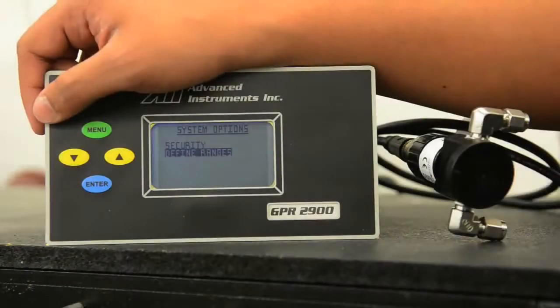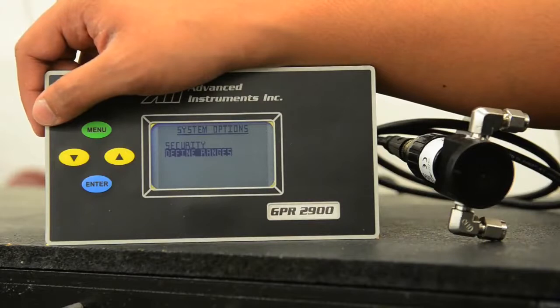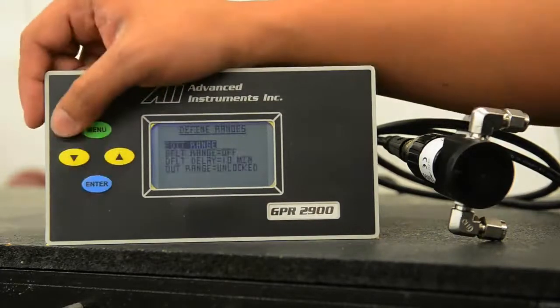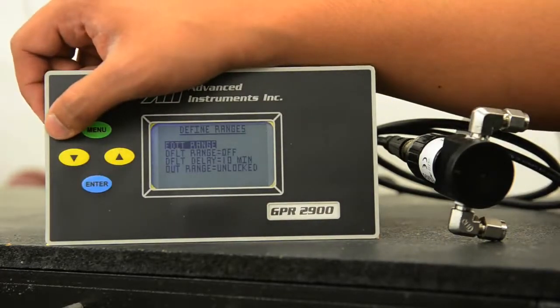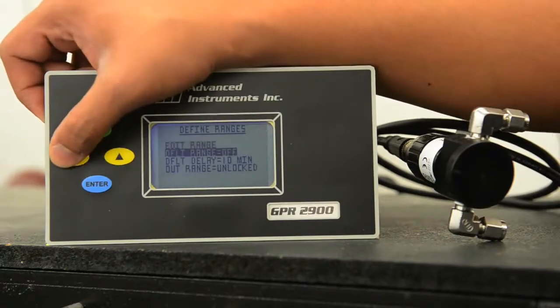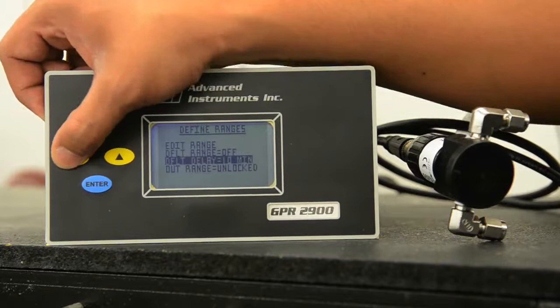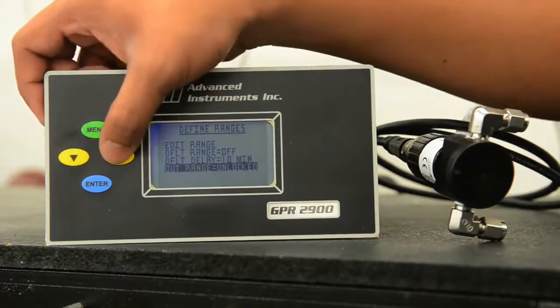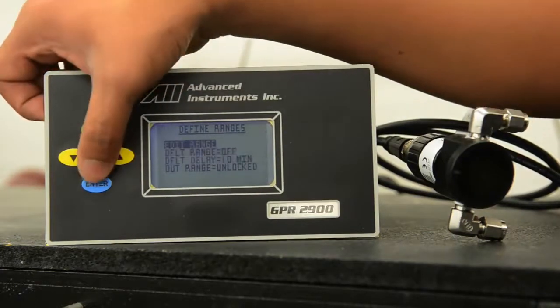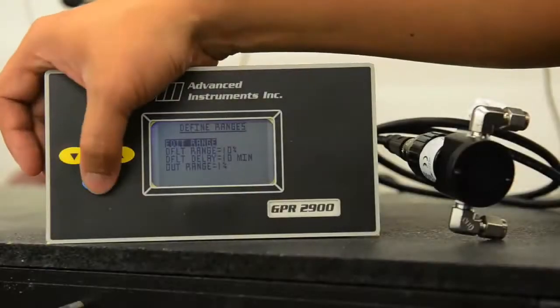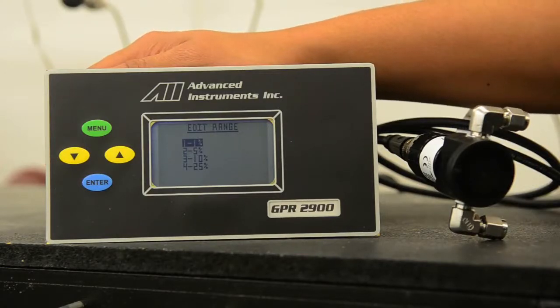Under the System Options menu, you also have the option for Define Ranges. If we select enter, we see on the Define Ranges menu we have Edit Ranges, Default Range option, a Default Delay Range option, and an Out of Range option. We'll go over the Edit Ranges option. If you go to the Edit Range option, you can see this analyzer comes standard with 4 ranges, 1%, 5%, 10%, and 25%. These ranges can all be user configurable.